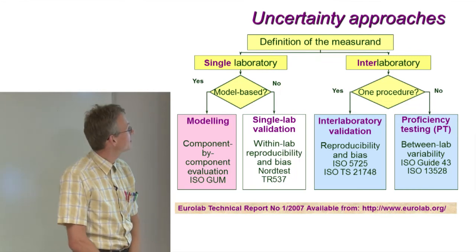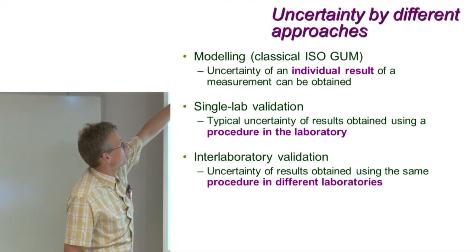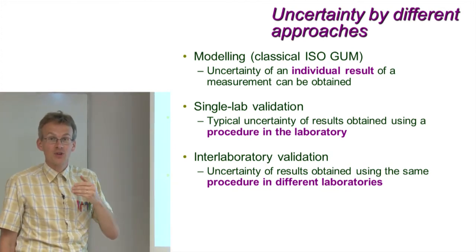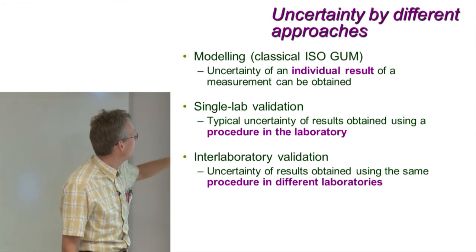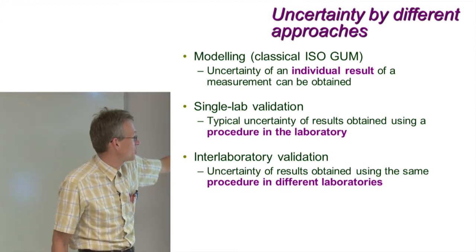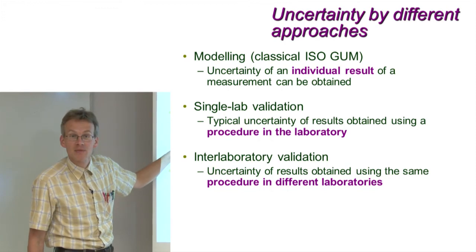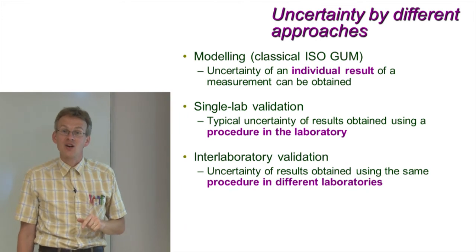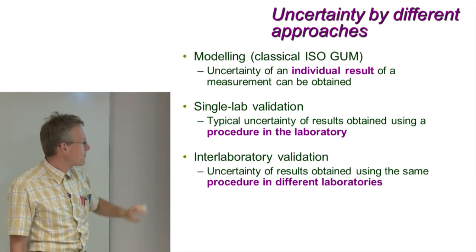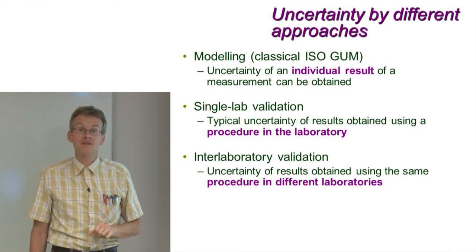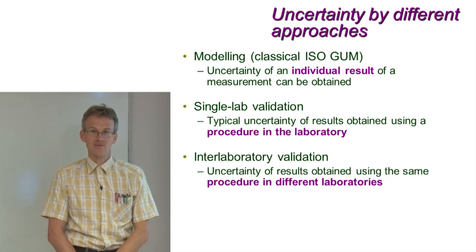The approaches give uncertainties that refer to different situations. The modeling approach calculates the uncertainty for an individual actual result obtained on one concrete day with one concrete sample. The single lab validation approach calculates a typical uncertainty of results obtainable with a particular procedure, so the uncertainty estimate is linked to the procedure rather than to any particular sample. The interlaboratory approaches give a general typical uncertainty that can be expected from the procedure when used across different laboratories.